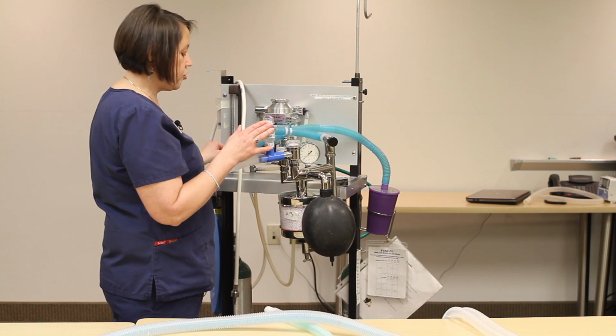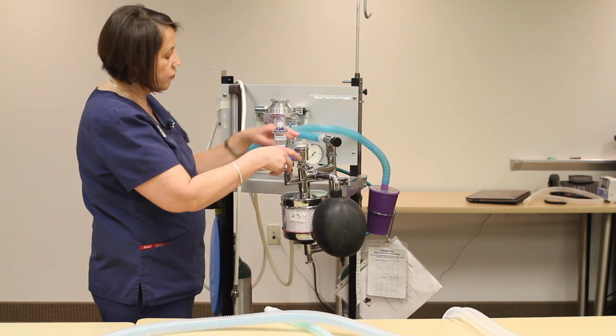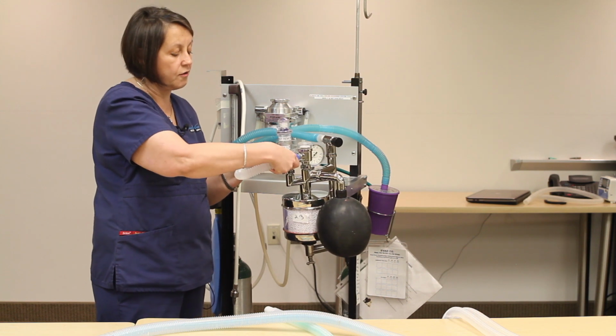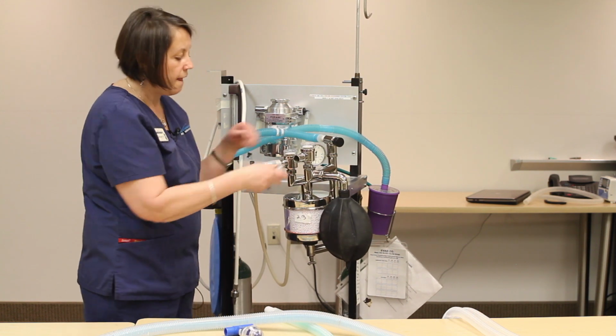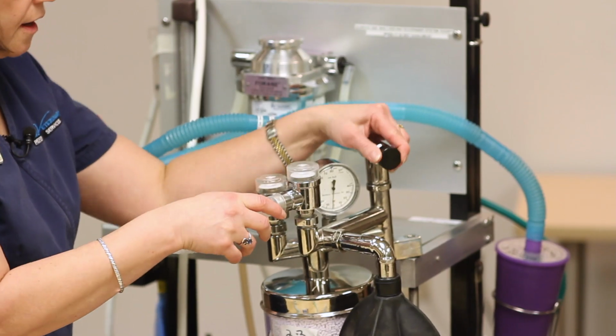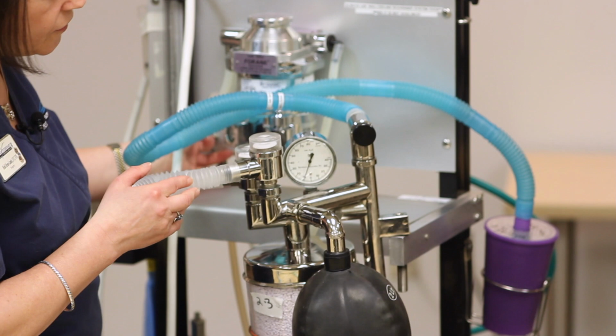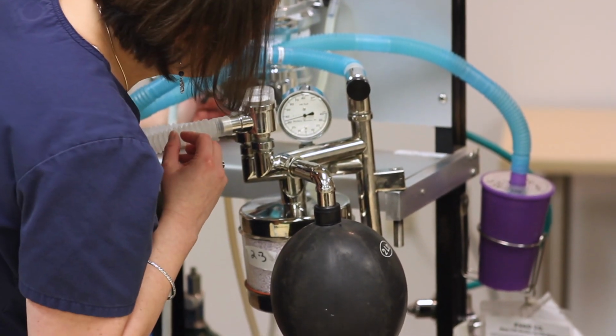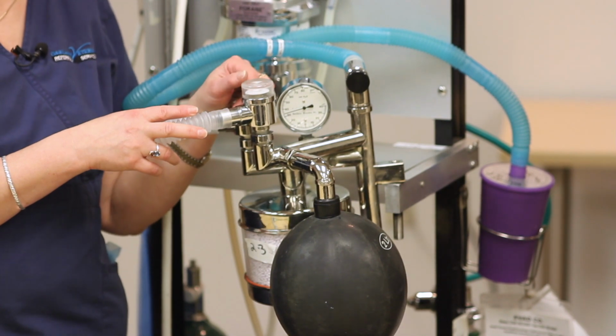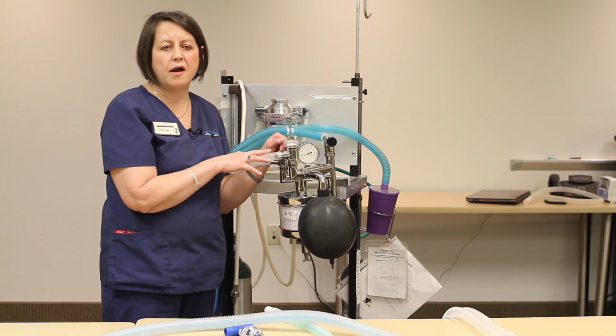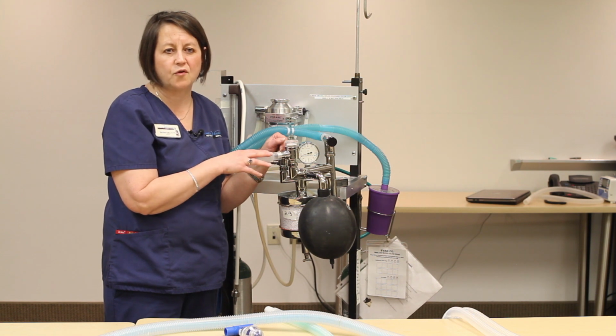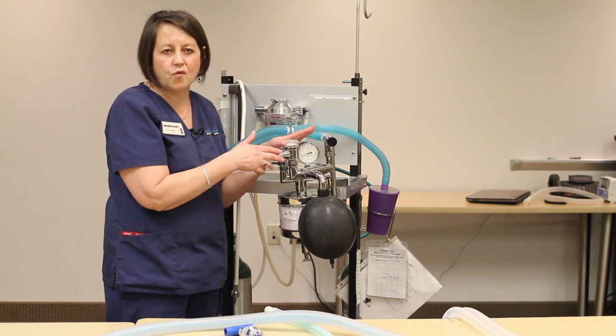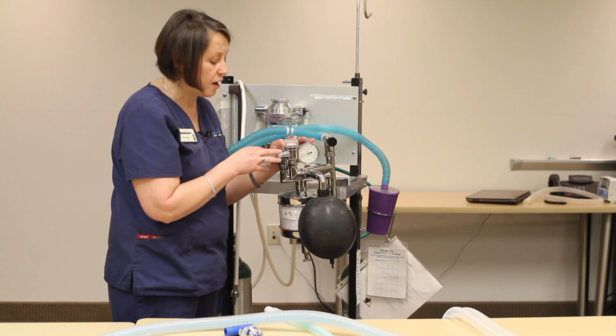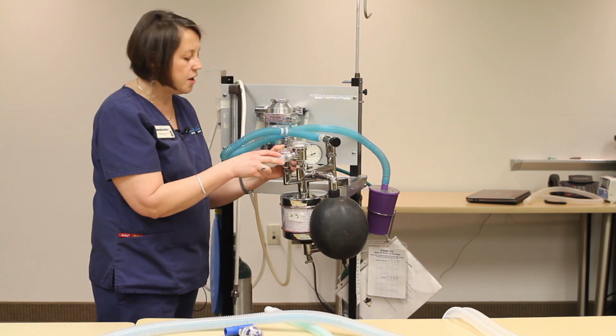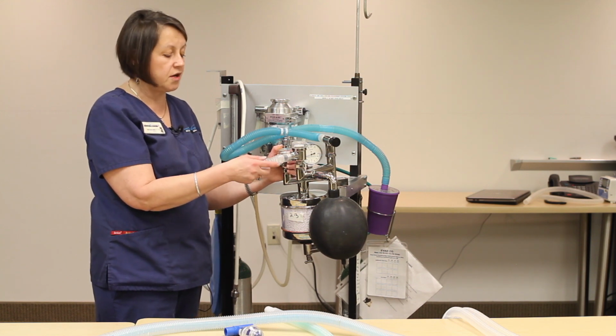You also want to check the machine without this safety feature, so we'll make sure that that safety feature is working correctly. But we'll go ahead and pull that off, and then we'll recreate our dead end. And again, I'm going to push the oxygen flush to pressurize the circuit. And we're going to just check that right to about 30 centimeters of water, since I would never, in my right mind, ever bag an animal to over 30 centimeters of water. So I don't really care if it's going to leak at pressures over 30 centimeters of water. This particular machine, all of our machines are newer machines, and they're very tight machines. They don't leak at all.